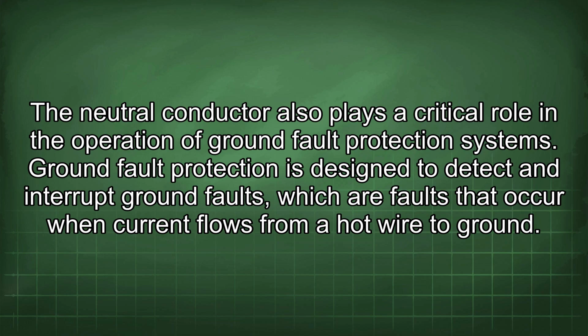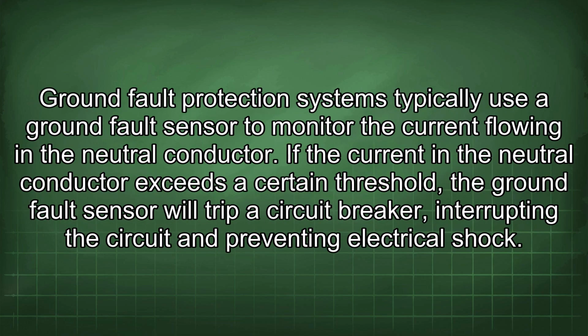Ground fault protection is designed to detect and interrupt ground faults, which are faults that occur when current flows from a hot wire to ground. Ground fault protection systems typically use a ground fault sensor to monitor the current flowing in the neutral conductor. If the current in the neutral conductor exceeds a certain threshold, the ground fault sensor will trip a circuit breaker, interrupting the circuit and preventing electrical shock.